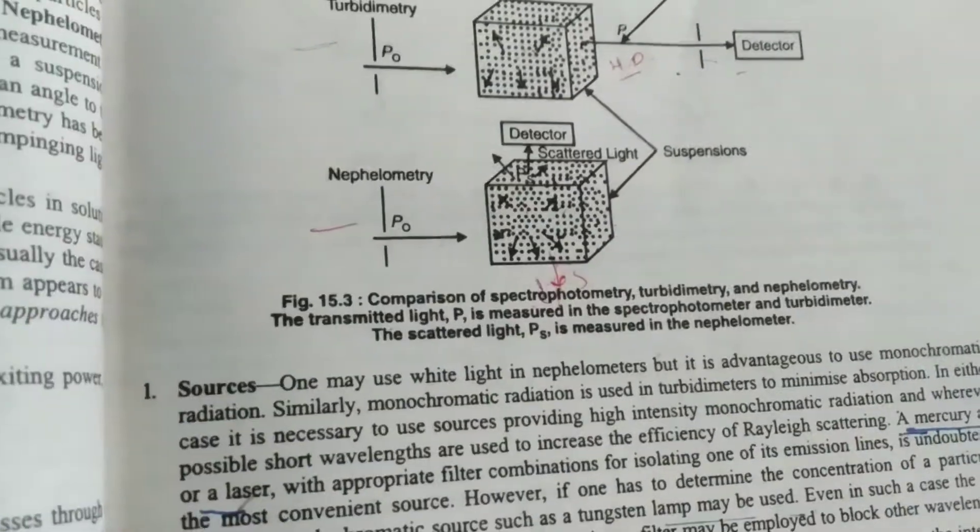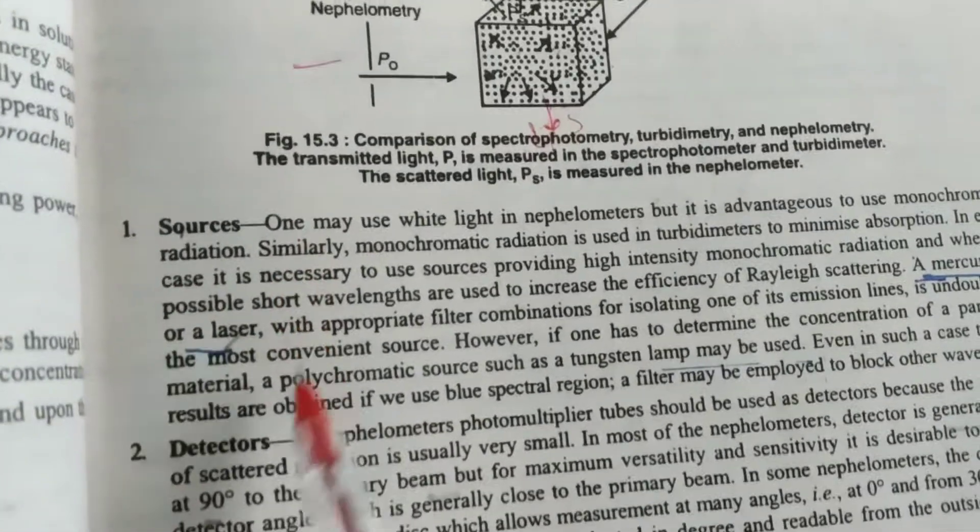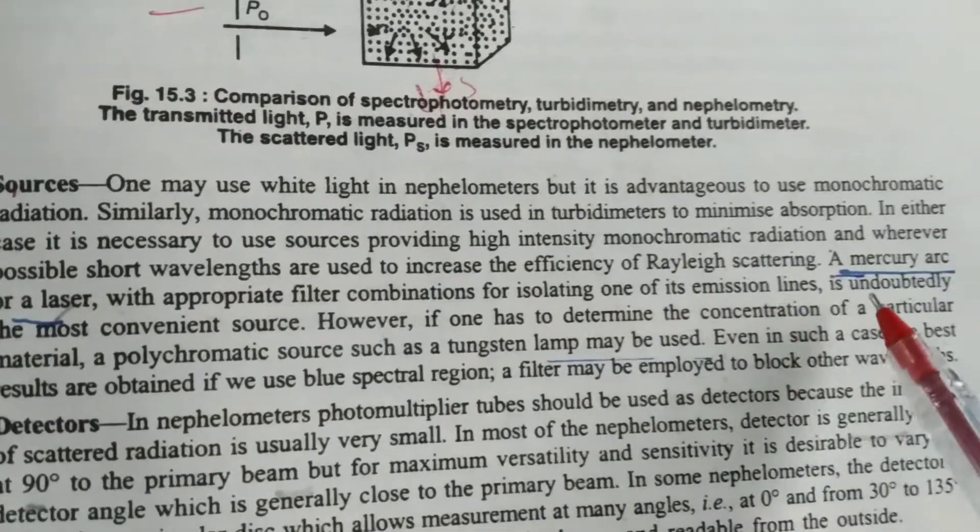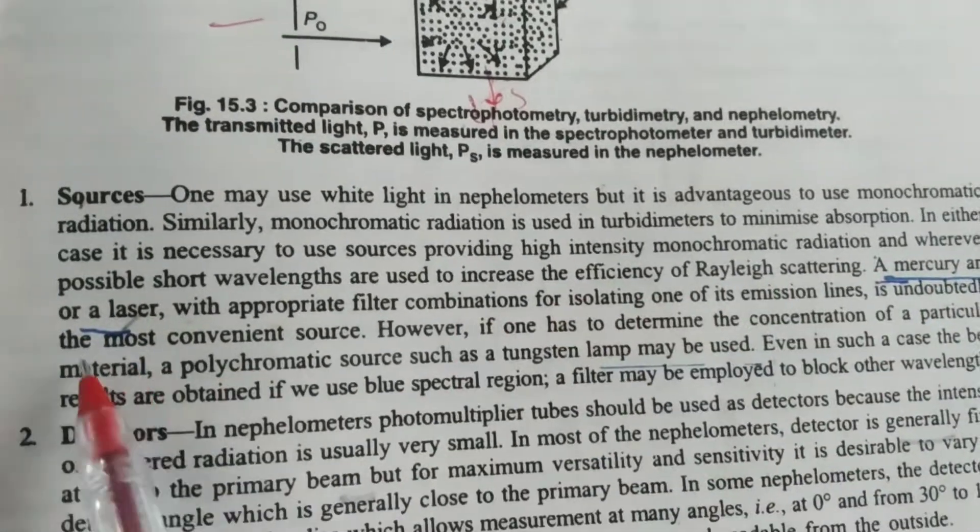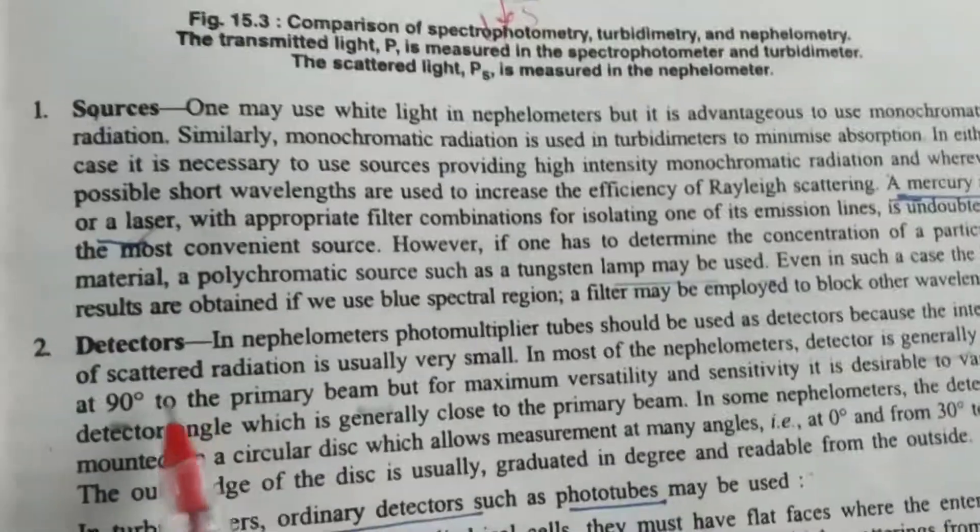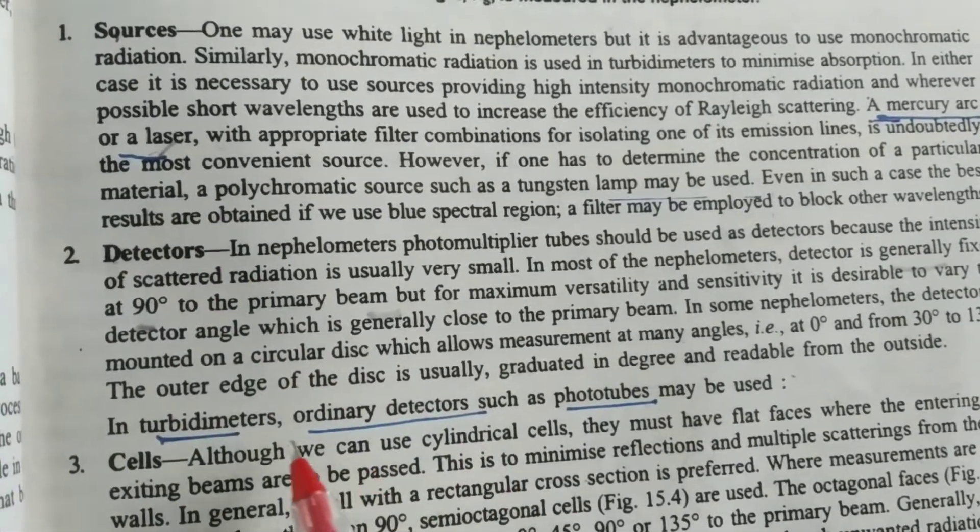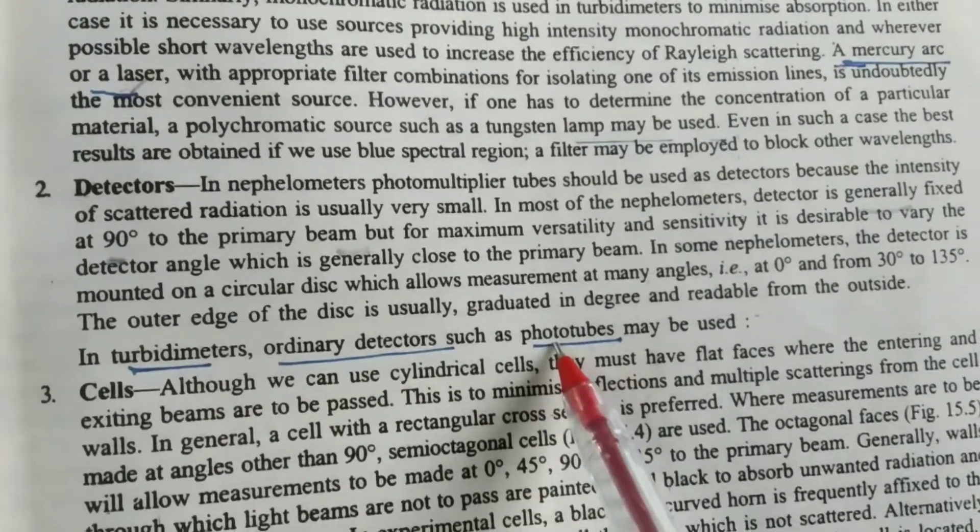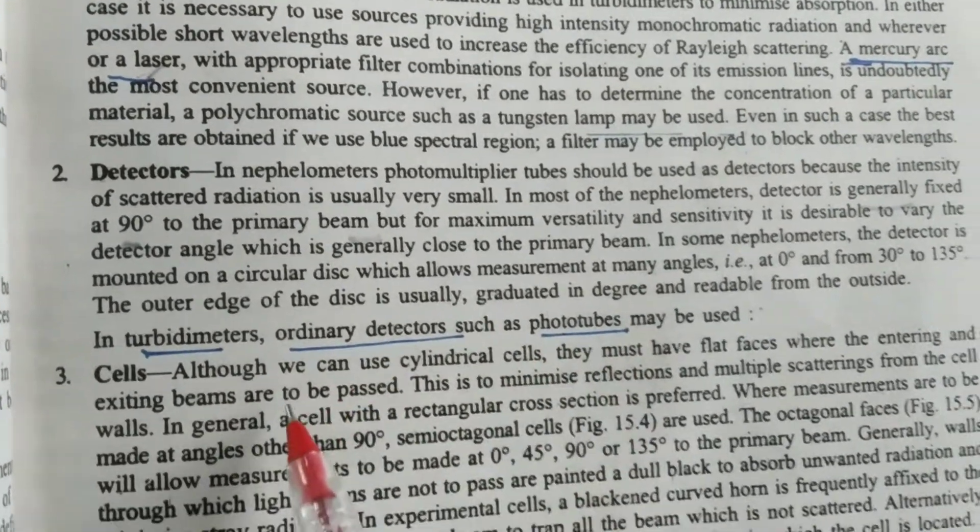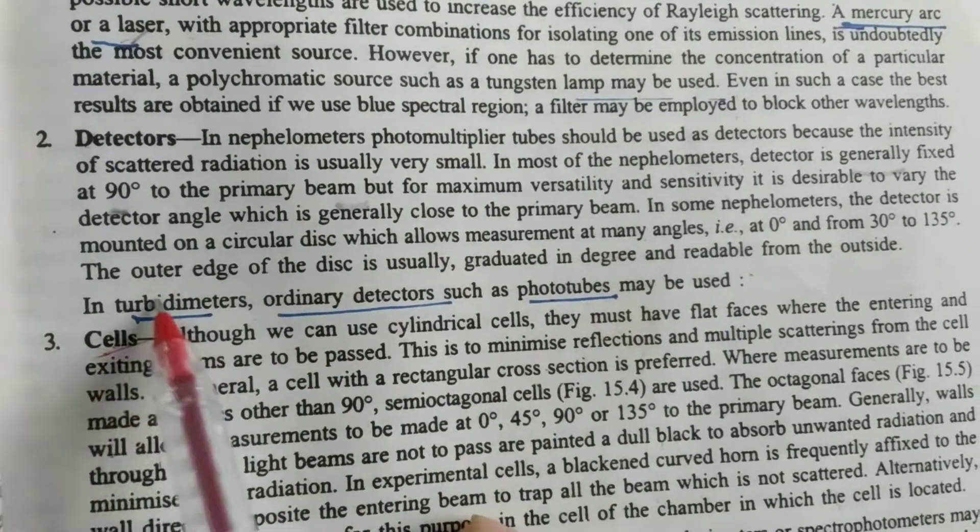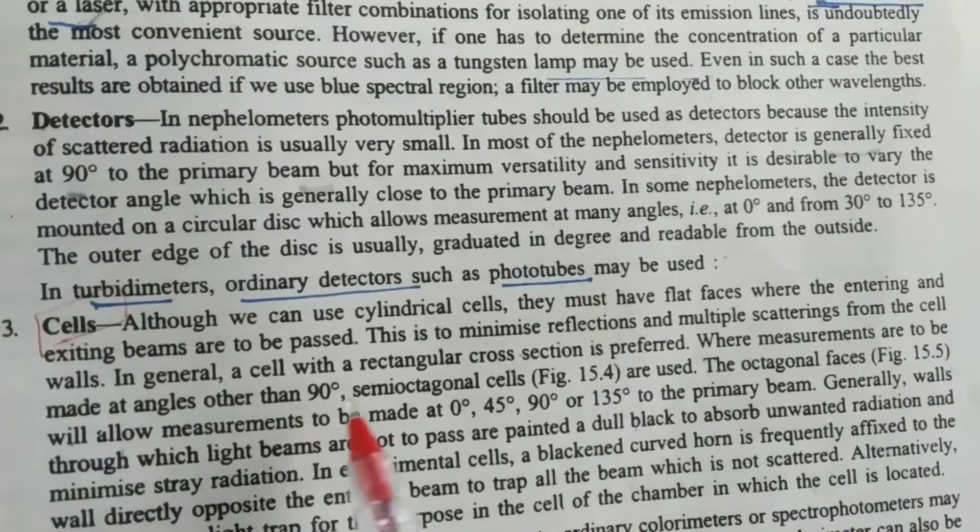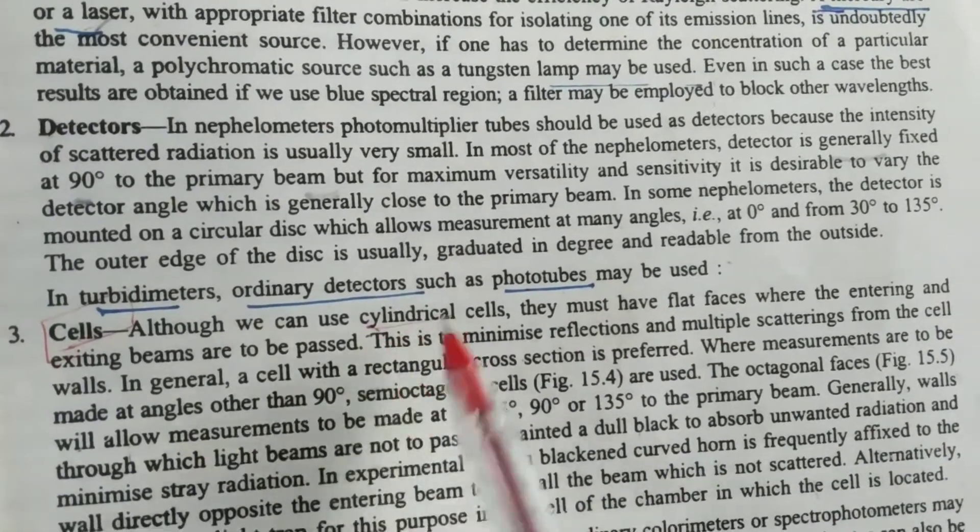The general instruments are light source, detector, and cell. In turbidimetry, the light sources generally used are mercury arc or laser. Detectors are ordinary detectors such as photo tubes. Cells or cuvettes are like quartz cuvettes, which are cylindrical cells.